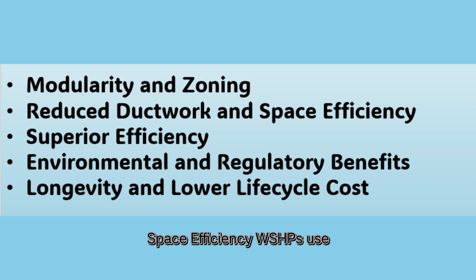B. Space efficiency. WSHPs use small diameter piping to carry large amounts of thermal energy. For perspective, a 2-inch water pipe carries the same cooling capacity as a 24-inch air duct, saving significant ceiling space. The loop can also serve domestic water heat pumps, DOAS units, and even water-cooled VRF systems.